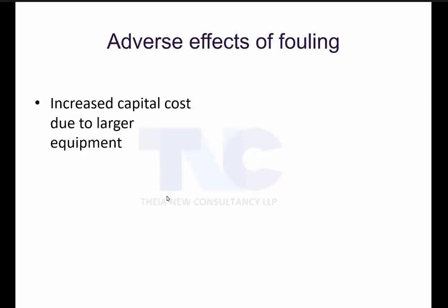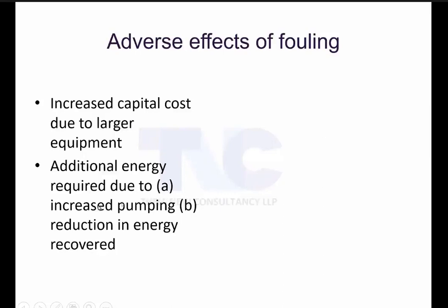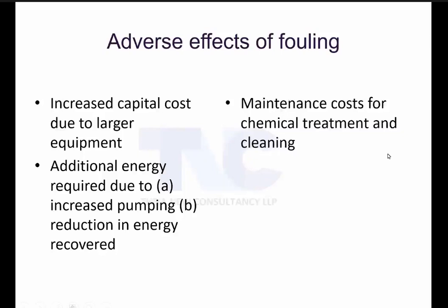Another problem with fouling is additional energy required due to increased pumping, because when there is fouling you will have pressure drop. When there is more pressure drop, as I said in the beginning, one of the signs of a problem is that the power of the pump will go up. Then maintenance, the biggest headache: you take it out, pull it, chemically clean it, and that is a lot of maintenance cost. Downtime cost is very important. Sometimes the cleaning will take one day, two days, three days, depending on the amount of fouling.